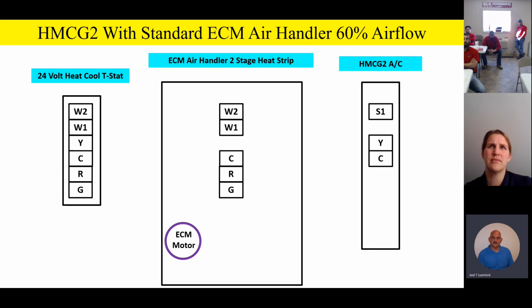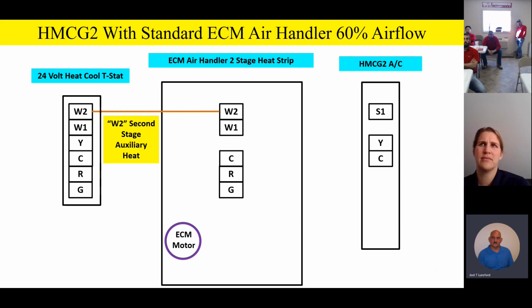As we take a look at it, it's a simplified block wiring diagram, but you can notice on the outdoor unit that we don't have the B terminal and all that, because it's a straight cooling product, so we won't be utilizing a B terminal. If we do have an ECM type of air handler, this would be an H or a JHET air handler or the legacy AE air handler. W2 will be second stage auxiliary heat. W1 will be first stage. This is looking familiar to you. It's going to wire exactly like we had before.